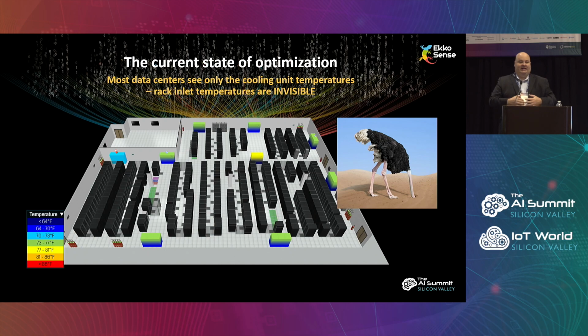So if you look at the way data centers are operating now, what you see on the screen is a representation of a typical data center. Where you see color, that's the cooling units. That is where they're measuring and understanding what they're providing to the operation. All of the black racks you see in there, that's the IT load. That's the server infrastructure, the compute, the storage, the networking, the connectivity. Most operators are blind to what's actually happening thermally and from a power consumption standpoint when it comes to the actual cabinets. And remember, those are the things that cause the need for the data center to begin with.